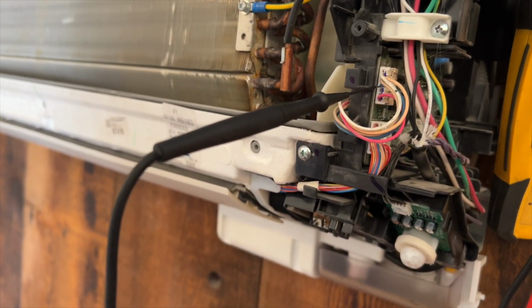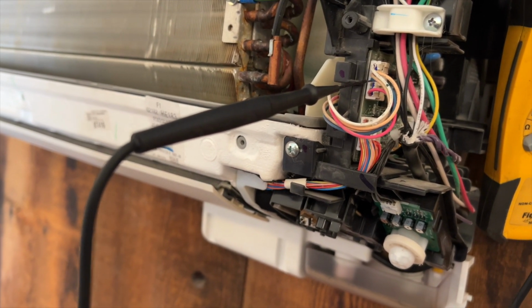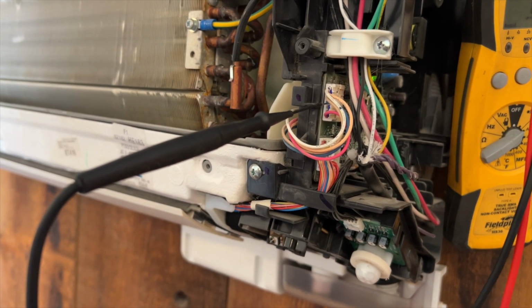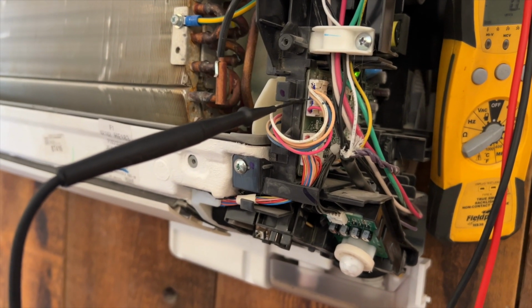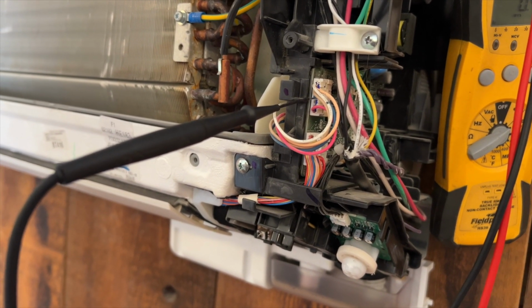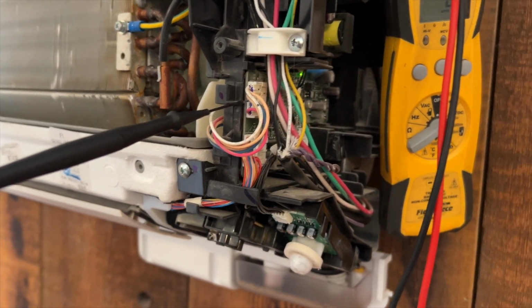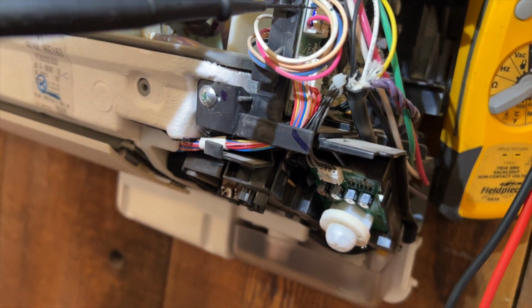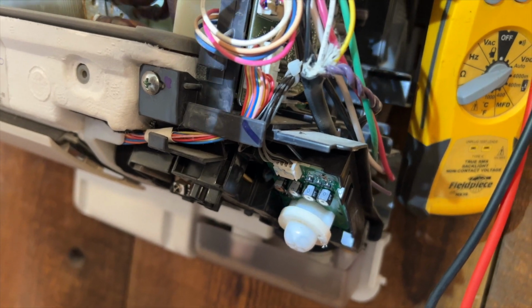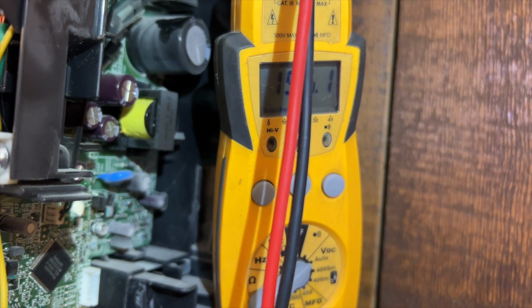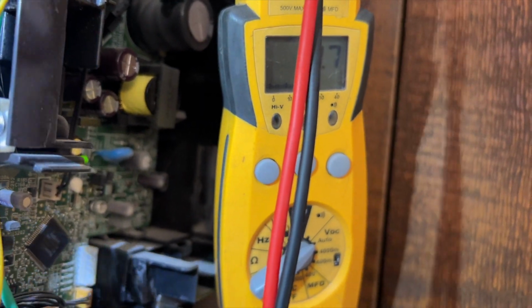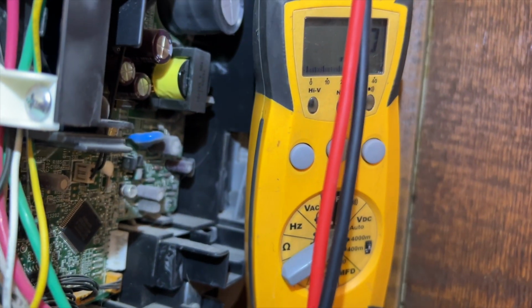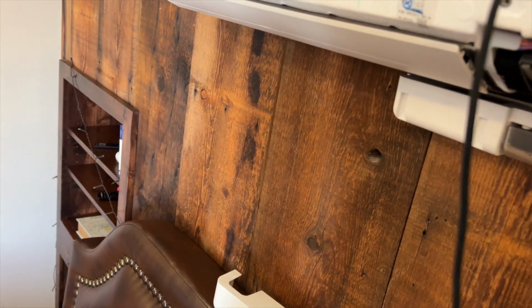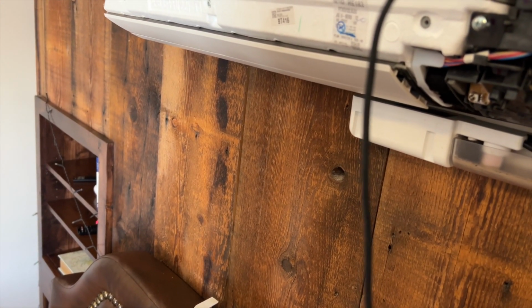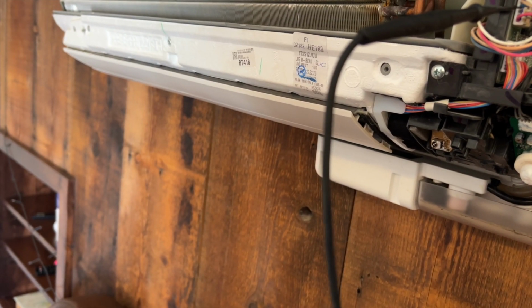And then the next thing we want to check is we're going to check our rotation command voltage, which should be 1 to 5 volts DC, and that's going to be between 4 and 2. Okay, so we got 1.3. All right, so the only thing that we're having a discrepancy on is our motor control voltage.